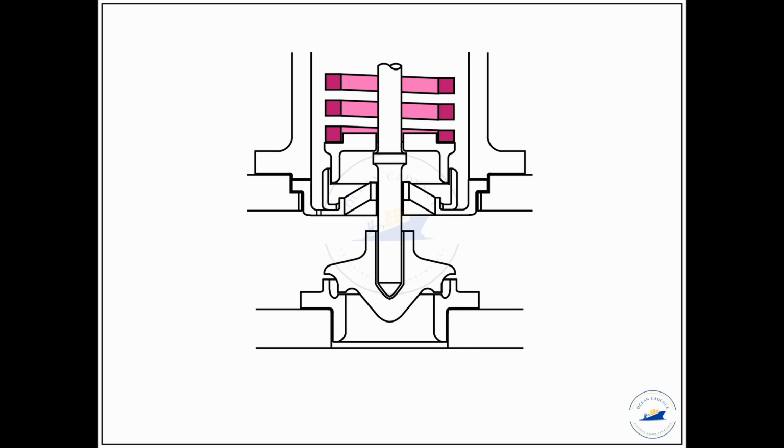So, for testing this spring, we have to make sure that we have a spare spring as well, so that we can compare the actual length of the spring, that is the free length of the existing spring which is in use, with the new safety valve spring. We have to make sure that there is no degeneration in the free length of the spring upon comparison.